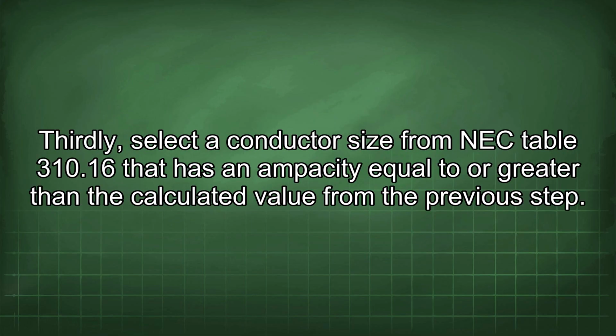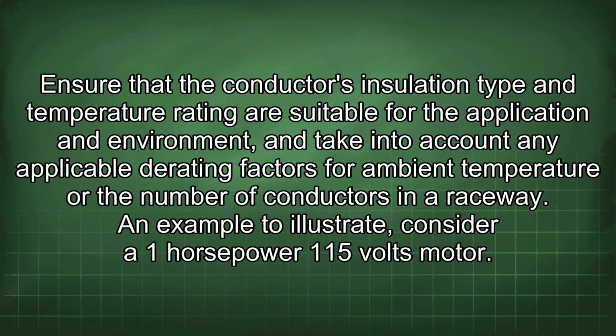Thirdly, select a conductor size from NEC Table 310.16 that has an ampacity equal to or greater than the calculated value from the previous step. Ensure that the conductor's insulation type and temperature rating are suitable for the application and environment, and take into account any applicable derating factors for ambient temperature or the number of conductors in a raceway.